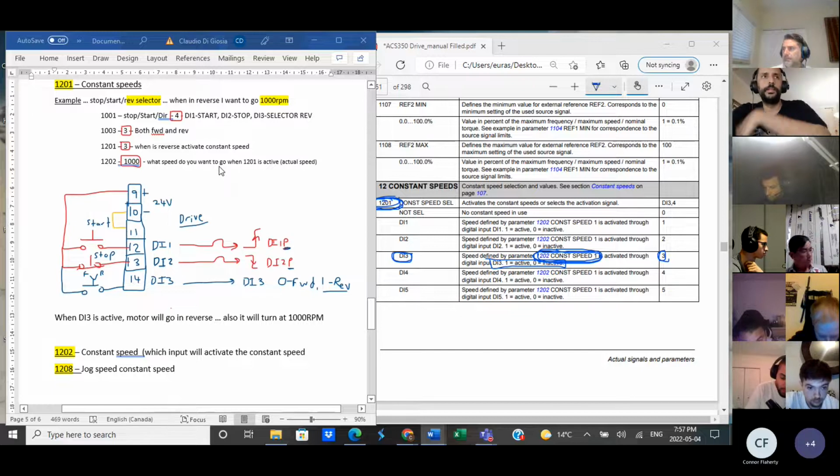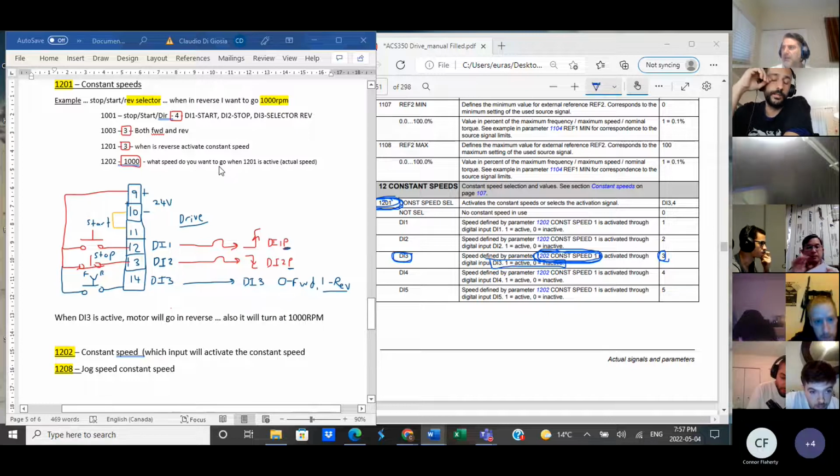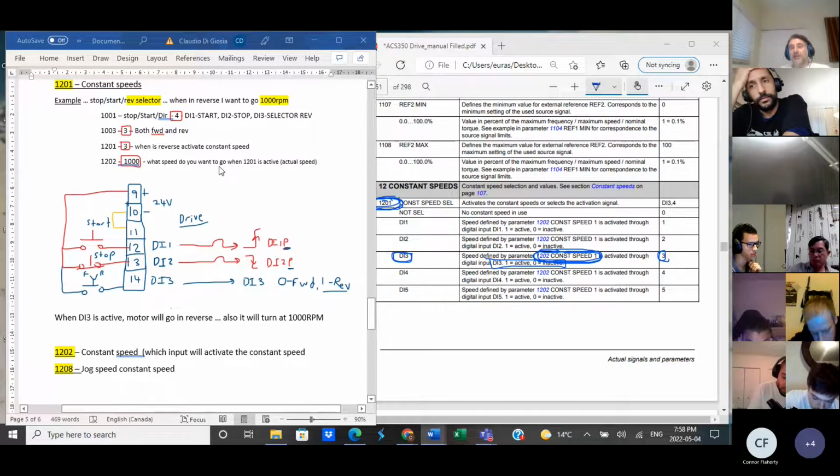How does it know what the speed is? Yeah, because it depends on the number of poles of the motor. Oh, that's a good question, actually. You have to configure the actual drive and input all that. So at the very beginning, the first lab you're going to be doing, and we'll see it tonight, well, if we get that far tonight, we're going to go to the 9900s, 9905, 9906, 9907.